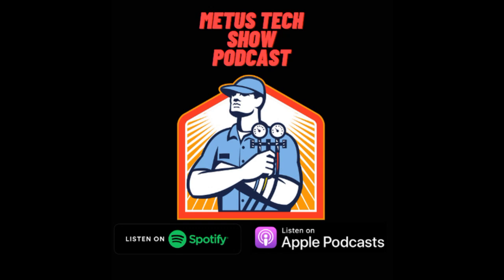For those of you that never heard of Diamond System Builder, it's free software available on mylinkdrive.com. You go to the software tab, download Diamond System Builder. It's going to allow you to build a one-to-one or multi-zone system, either residential or commercial, and lay out all of the pipe sizes. You can enter in your pipe lengths, your heights, because Diamond System Builder is looking at two major things when you're building that system out: your maximum pipe lengths, not exceeding that, and your vertical separation. Those are the important things. And at the end of it, it tells you how much refrigerant to add.